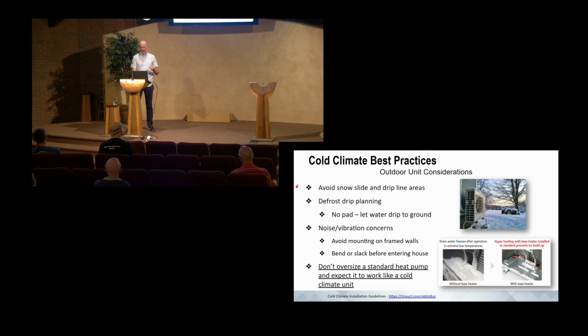A couple key points with heat pumps outside: avoid the snow line, the drip line, right where the roof comes down and the water drips. You don't want that water dripping on the heat pump and refreezing, it'll throw it off in a number of ways, so just avoid it. It's okay if the drip line extends past the heat pump, say 6 inches or a foot in front. I'm okay with that, but just know you might get some dripping water on the fans, which can start to create imbalance on the fan. You want to avoid that.